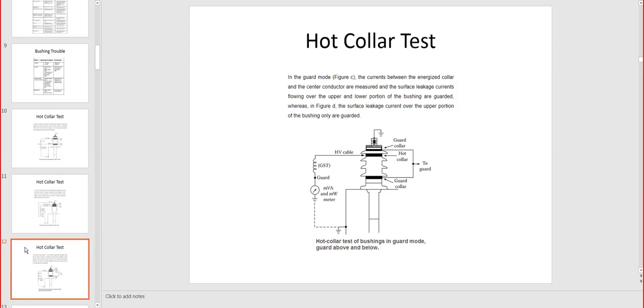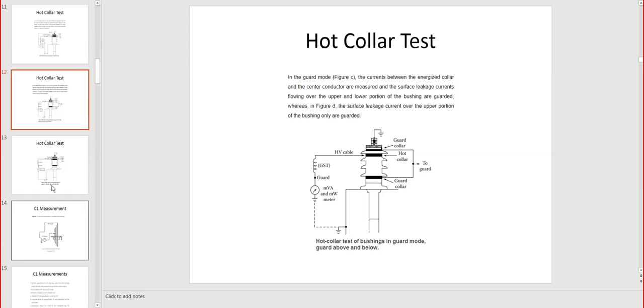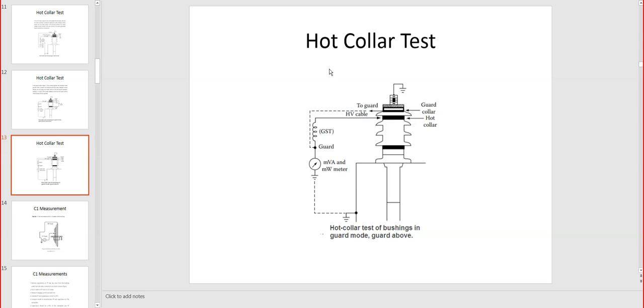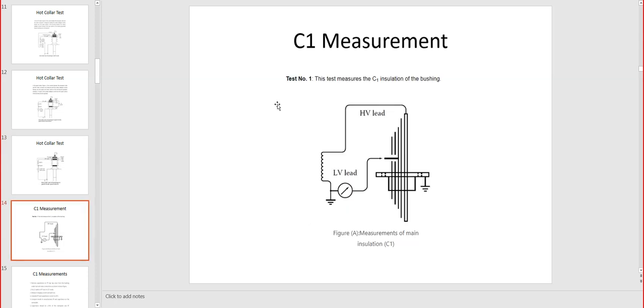So this is guard mode. There are different modalities of connecting or doing the test. They all do the same actually. Another one here, similar to the previous one, but you can see the second ring is not grounded in this position. We measure the C1. This one is more symbolic and is representing the reading that we're gonna have for the actual C1. So C1 from the top of the bushing to the tap, with the tap grounded. So this is the typical measurement that we do.